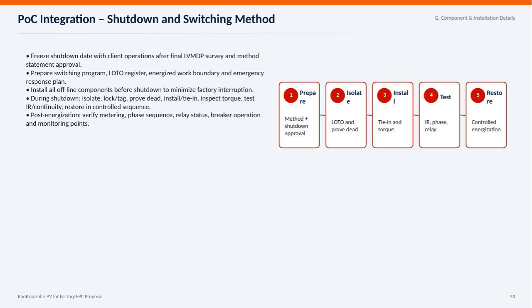Isolate the system, apply lock and tag procedures, confirm the system is de-energized, perform the installation and tie-ins, check all torque connections, and conduct insulation resistance and continuity tests. Finally, once the system is re-energized, we verify metering accuracy, confirm phase sequence, check relay status, ensure breaker operation, and monitor all relevant points to ensure everything is functioning safely and correctly. This systematic approach ensures a smooth and controlled integration process.